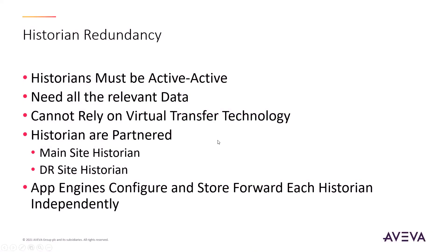Historians are part of the redundancy scenario and must be active-active — you can't have a historian in a passive state. They need all the relevant data. Historians are partnered: in this demonstration, a main site historian and a DR site historian are synchronized. The app engines do all that synchronization — they synchronize the configuration and the store forwarding to each historian independently.